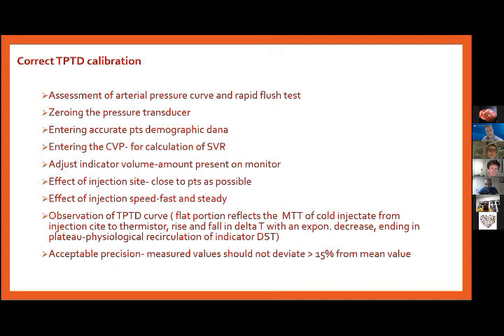It normally has a flat portion that reflects the mean transit time of the cold indicator injected from the injection site to the thermistor. Then it rises and falls, the delta temperature, as an exponential decrease. And again, it ends in a plateau, which is the physiological recirculation of the indicator, and we call it the downslope time.